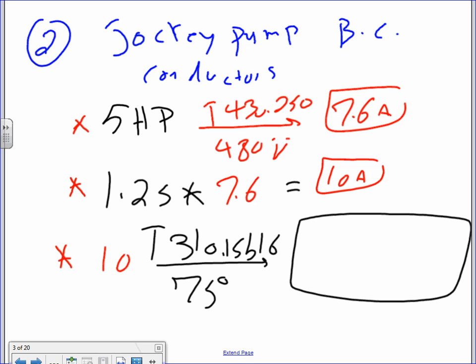And you take the 10 amps, and that will get you 3 conductors, number 12 AWG RHW. Is 12 the smallest they're supposed to go? You're absolutely right. So can I use 14? Yes. But you don't want to, in a commercial industrial building, don't even mention 14. Cool? You're absolutely right. The minimum, I could have gone with 14, right? You found 14, but you don't want to use that, 12. Does it make sense? 12 is your minimum in commercial industrial. Okay, next.